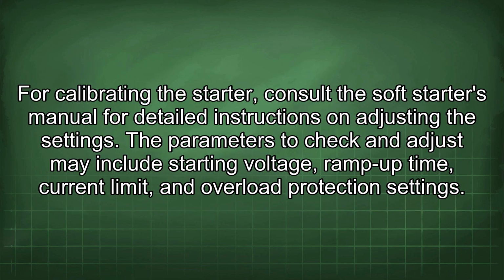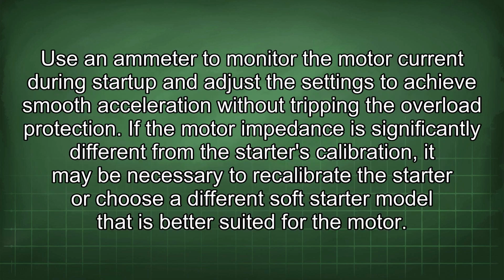For calibrating the starter, consult the soft starter's manual for detailed instructions on adjusting the settings. The parameters to check and adjust may include starting voltage, ramp-up time, current limit, and overload protection settings. Use an ammeter to monitor the motor current during startup and adjust the settings to achieve smooth acceleration without tripping the overload protection. If the motor impedance is significantly different from the starter's calibration, it may be necessary to recalibrate the starter or choose a different soft starter model that is better suited for the motor.